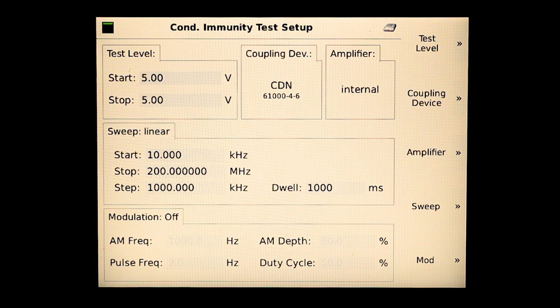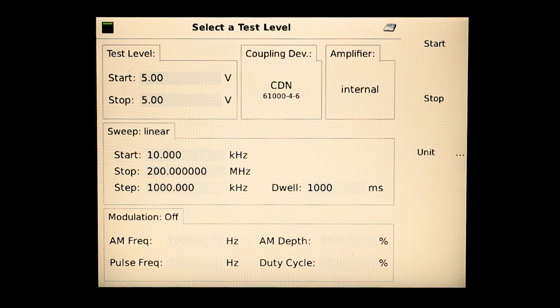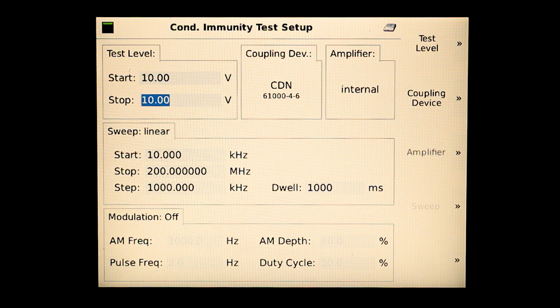To change the different criteria, go ahead and hit Test Setup in the upper right corner. And then this is where you can change the different criteria. So let's change the test level from 5 volts to 10 volts. Let's select the upper right button for test level. We're going to hit Start, and we're going to change that to 10 volts, and we're going to hit Enter. Now let's change the stop to 10 volts as well. Excellent. Now let's hit the back button. Now we're on our main display again.